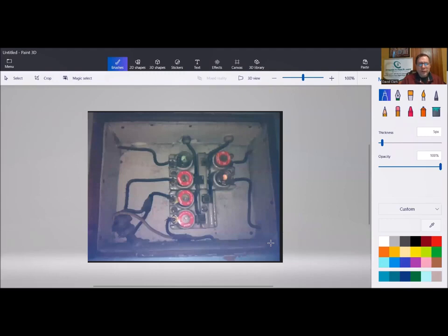Okay, so here's another spot. Fuse panel, an old fuse panel. And we could see it's lined with something, okay? And we pretty much know what that is. So we're going to recommend the panel is upgraded and replaced anyway. And so at that point, does it really need to be tested? I think the whole thing just needs to be taken out.